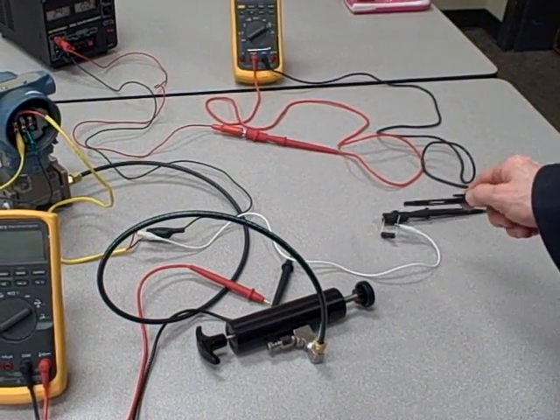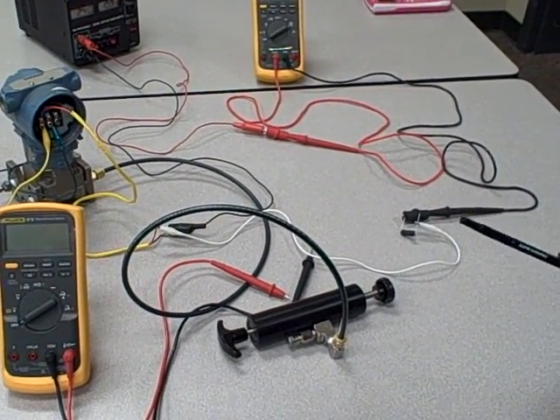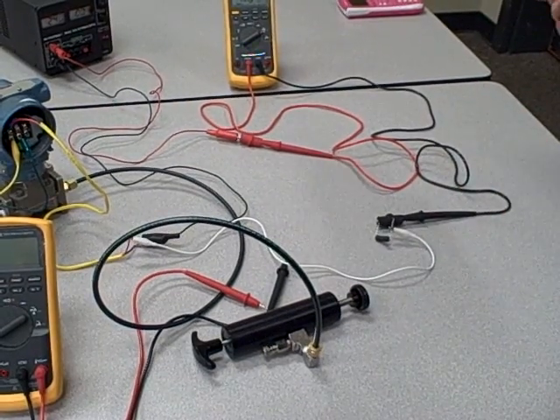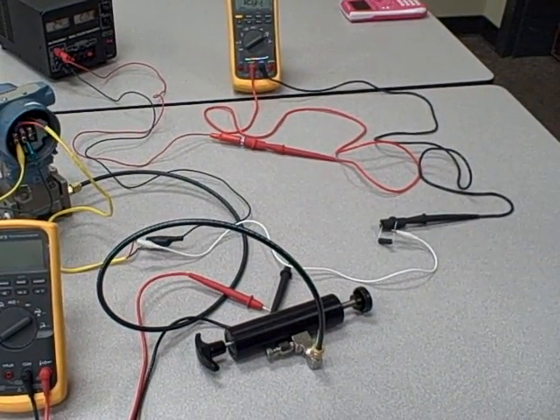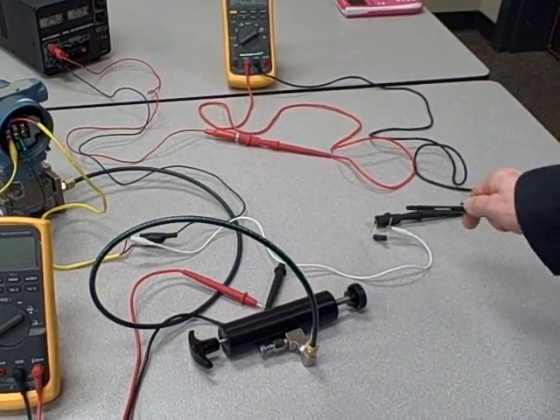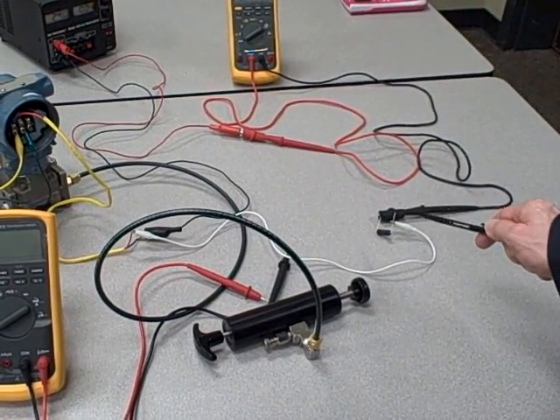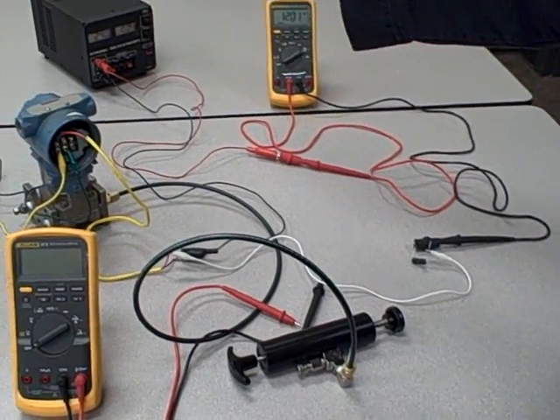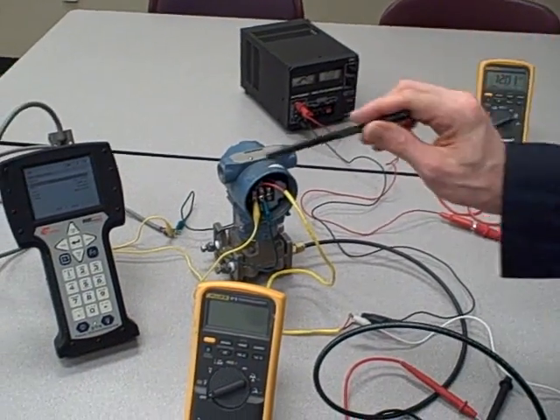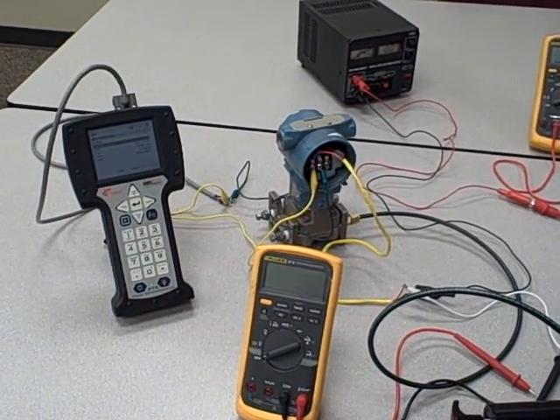And this loop resistance, again, does not have to be exactly 250 ohms. It can be anywhere from around 250 ohms up to about a thousand ohms. That's what Rosemount specifies. But some resistance does have to be in place in order that the DC power supply does not squelch the AC signals that the communicator and the transmitter are trying to generate.